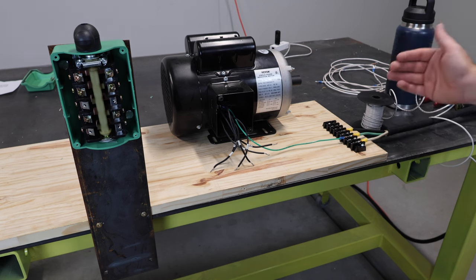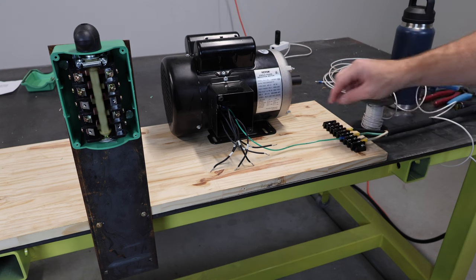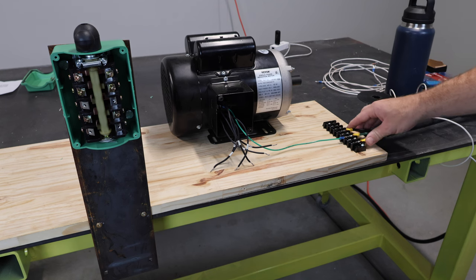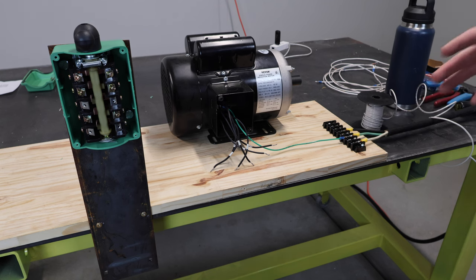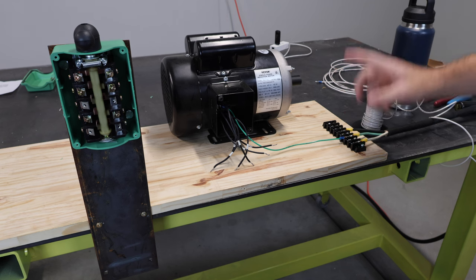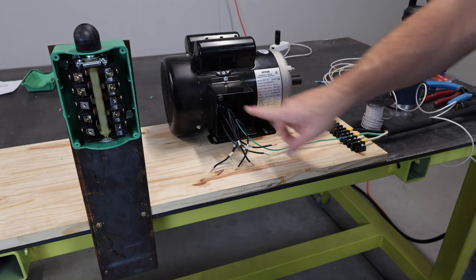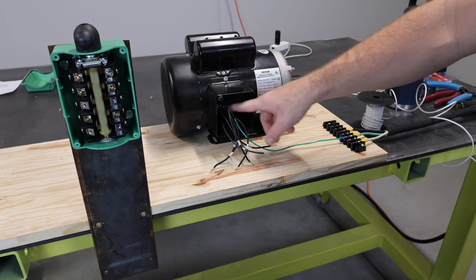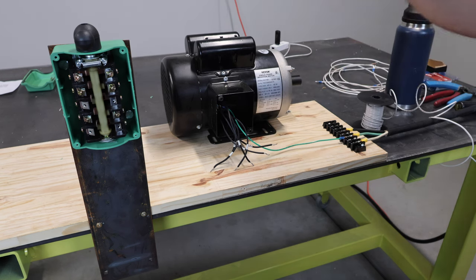Now, just so you guys know, L1 would be black and L2 would be the white wire and the green wire would be your ground, which I have going right here. If you do get these mixed up or switched, it's not going to make any difference towards the wiring system that you have, and it's going to work the exact same way. But, if you want to be absolutely correct, L1 is black and L2 is white. Now, I have my ground wire already going into the frame of my motor. If you looked inside there, there's just an actual bolt that the ground wire is connected to. This is just a nice safety feature, but I am working on a piece of wood, so it's kind of hard to have everything grounded.